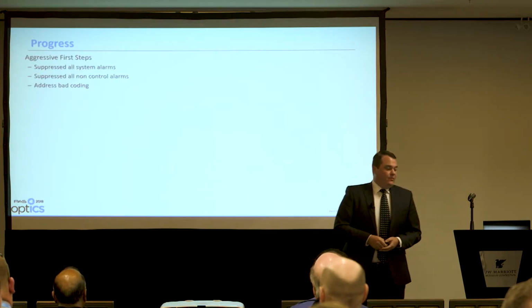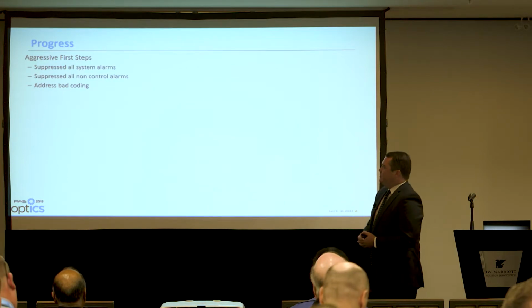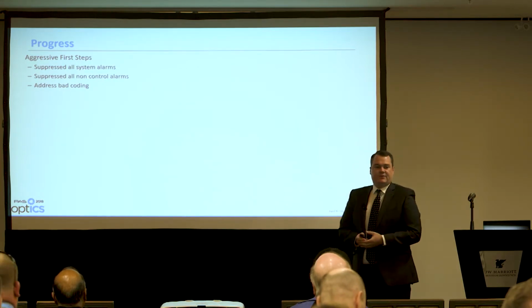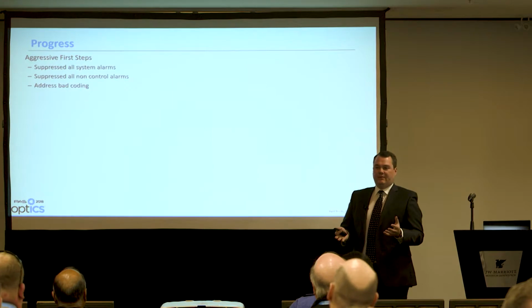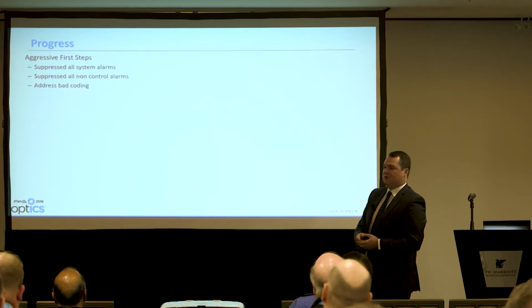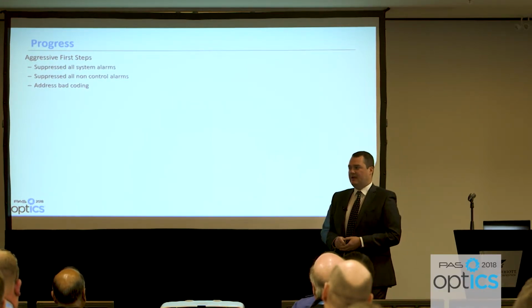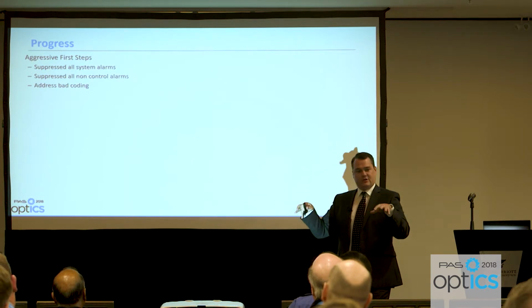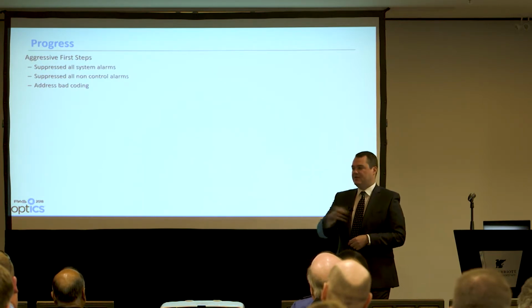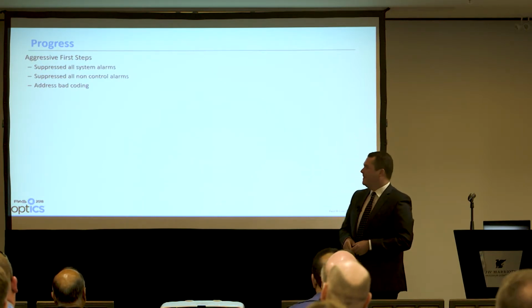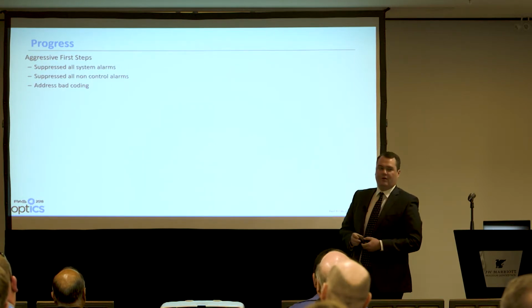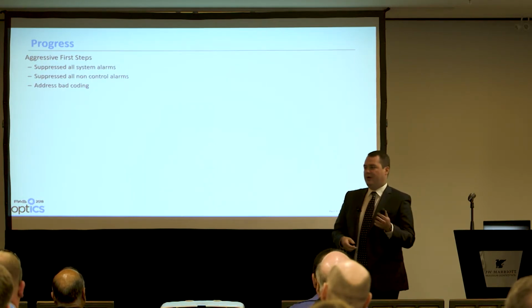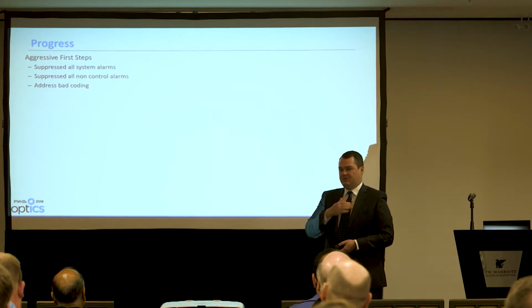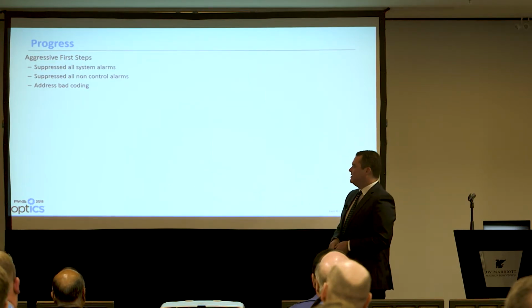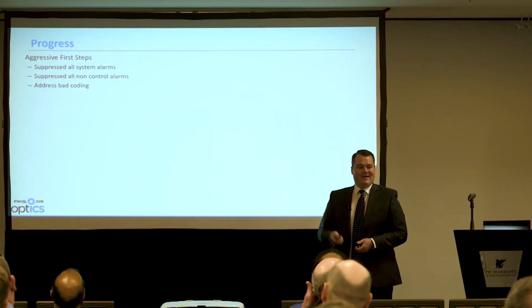So when we actually started, we took some really aggressive first steps. We said there's no way anyone can deal with that. What we did was suppress all system alarms — if there's an alarm telling us there's a problem with the control system itself, suppress it, the operator no longer sees it. We also suppressed all non-control alarms, all those nice warning reminders, just flat out suppressed them all without even rationalizing them, and started addressing the bad coding in there.